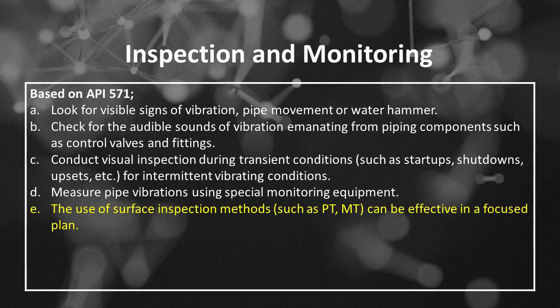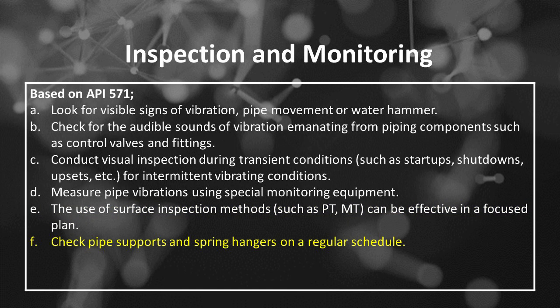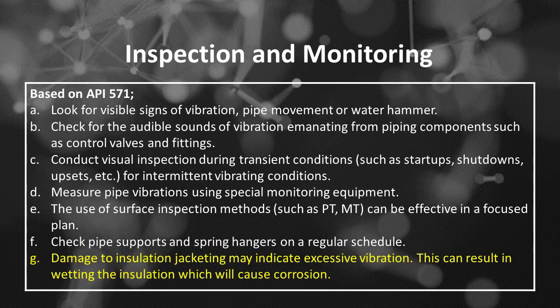The fifth is the use of surface inspection methods, such as PT, MT, can be effective in a focused plan. The sixth is check pipe supports and spring hangers on a regular schedule. The seventh is damage to insulation jacketing may indicate excessive vibration. This can result in wetting the insulation, which will cause corrosion.